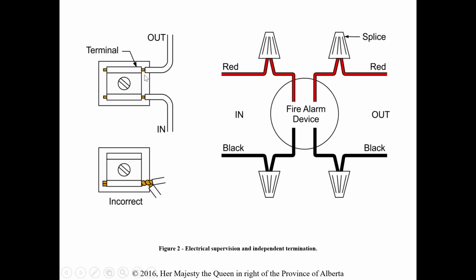But we might not ever want to do this. There are some instances I'll talk about where this is allowed, but it's a very specific instance. Okay. So in general, we do not want to splice them together. Otherwise, we take the device off and there's no difference in the circuit because these wires are still touching. Okay, so that's what they're talking about when they're talking about electrical supervision. Again, there is a caveat to that, and we'll talk about that coming up here.